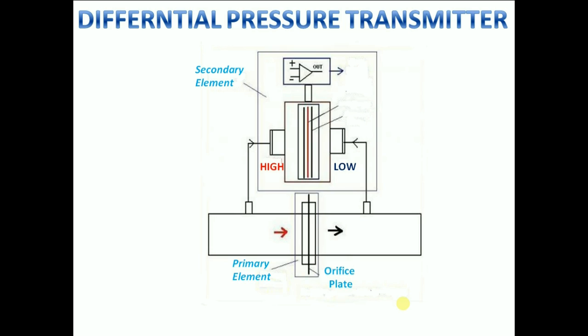The output signal from an industrial DP transmitter is likely to be 4 to 20 mA, but it may also include digital communications such as HART, Profibus, Foundation Fieldbus, Modbus 485 RTU or one of many other communication protocols.